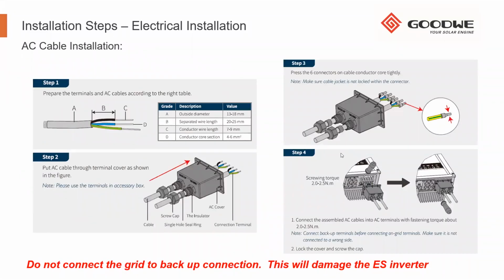For the AC connections, you'll see we've got the 2 ports as well. We also have in the manual the recommendation for the recommended conductor size and the wire length of the conductor, and you'll also find the ferrules in the packaging, just to make sure that we have a good connection for the cables that you are using. Using a ferrule like this also helps to prevent us sticking the cable in too far and securing it on the plastic of the cable. It's just good practice to make sure we use the ferrules.